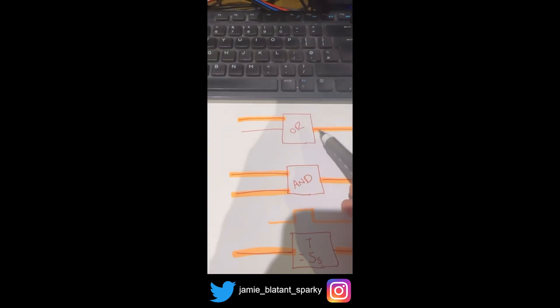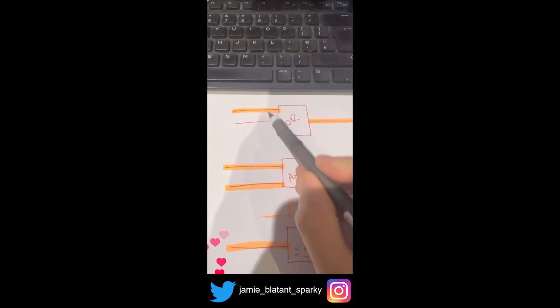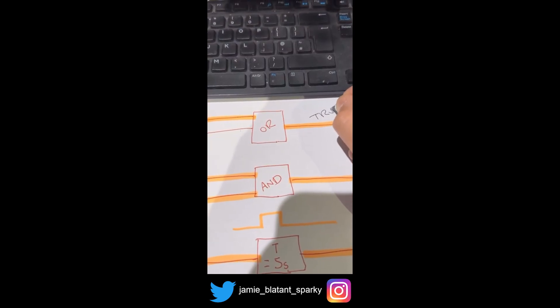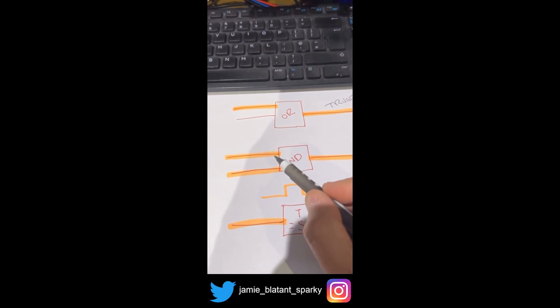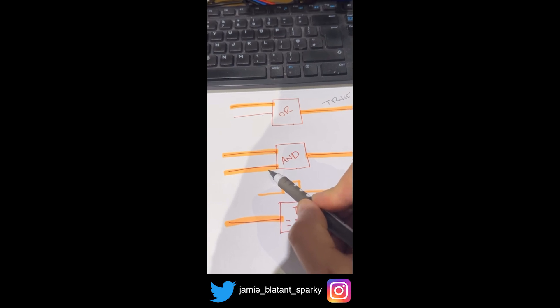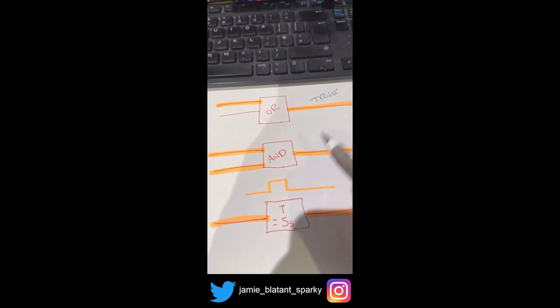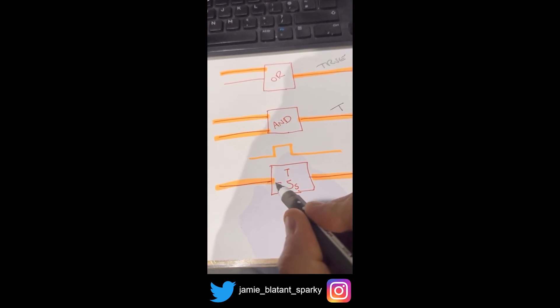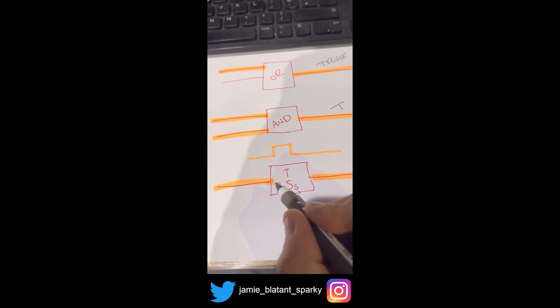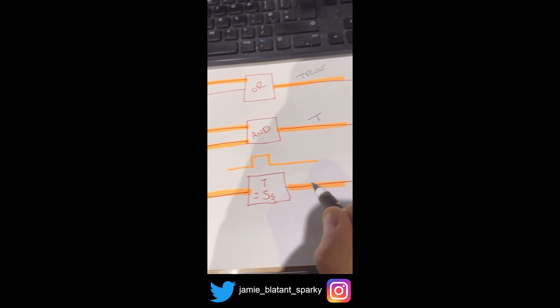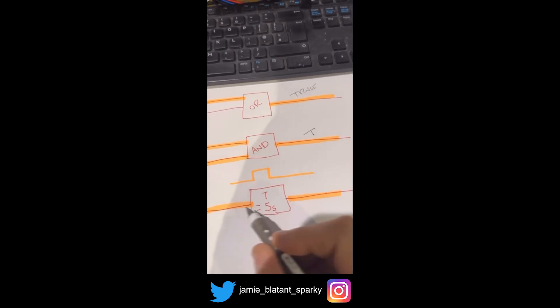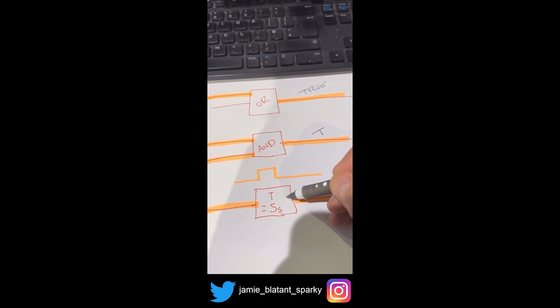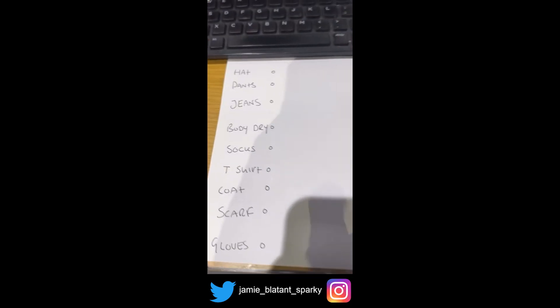These are the logic symbols you're going to use. OR means if this one is on or this one is on, this one becomes true. AND means that one has to be on and that one has to be on for it to become true. A timer — if you put something into here it'll go one, two, three, four, five because it's a five-second timer, and then it becomes true. It delays it while you're waiting for other things to happen. You're going to use OR gates, AND gates, and a timer.